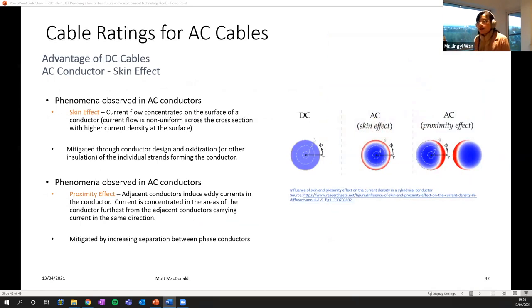And two other factors affect the rating of an AC system: skin effect and proximity effect. The electrons are unsociable bonds really, and they are negatively charged. As a result, they tend to go to the edge. And therefore there are two phenomena. The first one is the skin effect, and the second one is the proximity effect. Both of these effects mean we can't fully utilize the conductor. So the electrons are not distributed evenly. That is one of the reasons why, for the higher voltage, we choose to go with DC.